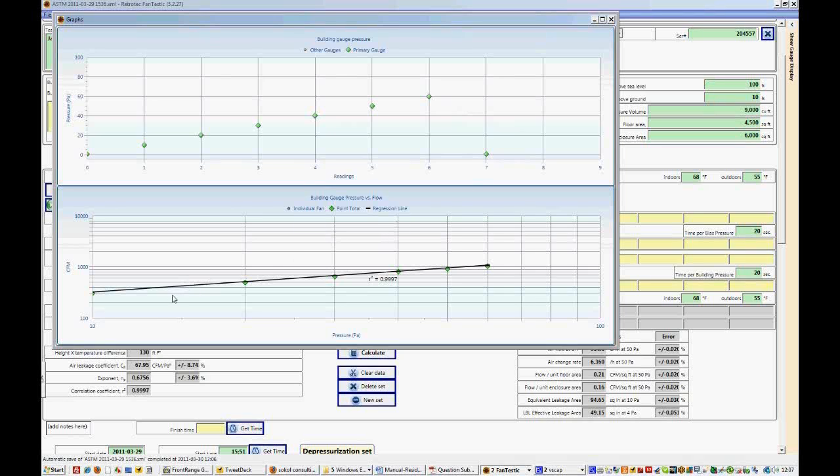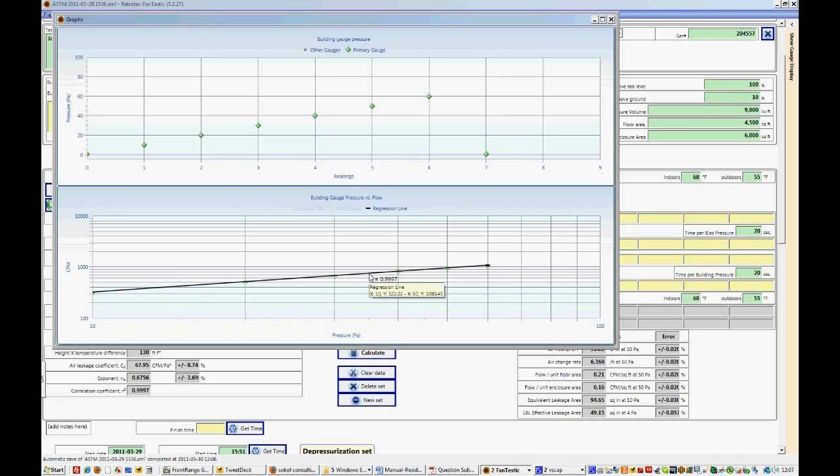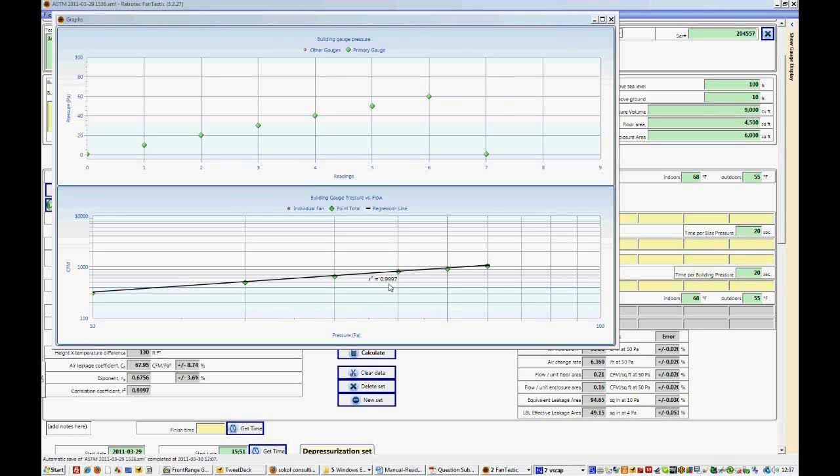Now on the second graph you'll see our flow on the y-axis and on the x-axis we have the pressures. And this is a log scale graph which is why the lines are not evenly distributed. And you'll also notice that this line runs through all these points and this is the regression line. The 99% or 0.9997 represents how closely this line matches or fits the data that it's running through. And this is an excellent regression.